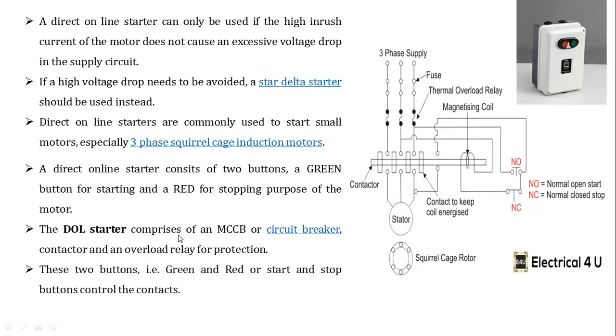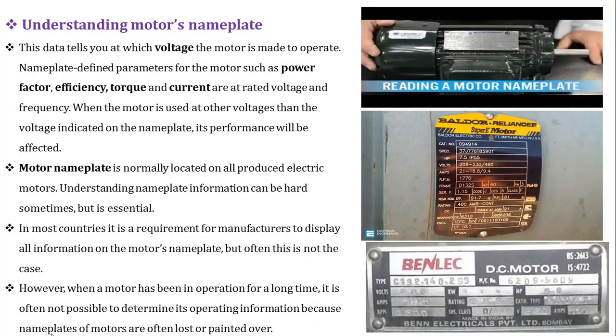The DOL starter comprises an MCCB or circuit breaker, contactors, and an overload relay for protection. So what exactly does it consist of? It comprises an MCB, the main circuit breaker, the contactors, and the thermal overload relay protection. These two buttons, green and red, or start and stop buttons, control the contactor over here. So this is about the DOL starter used to start a three-phase induction motor.